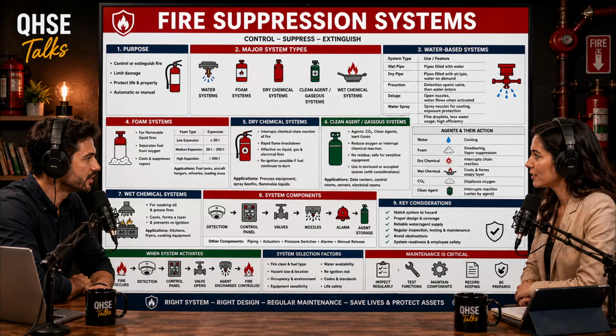And what does that thermal sensor look like mechanically? The most common modern type is the frangible glass bulb. It's a tiny, heat-sensitive glass vial. Inside the glass bulb is a liquid, usually a glycerin-based solution, and a tiny air bubble. Oh, I've seen those. They're usually red or green glass tubes.